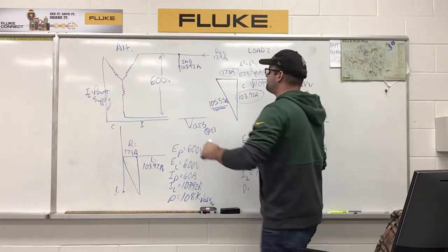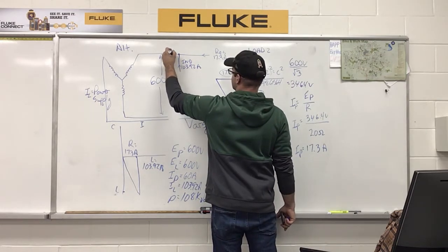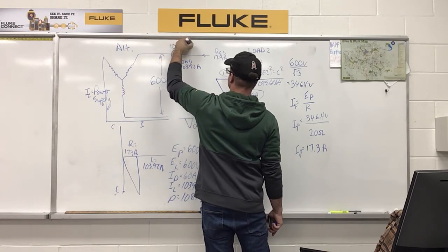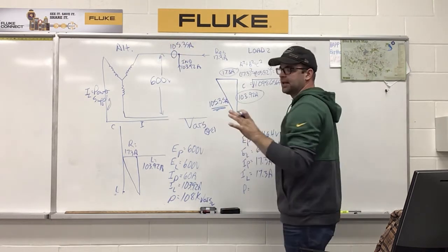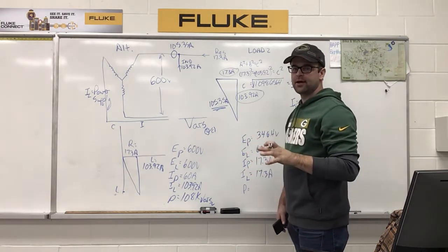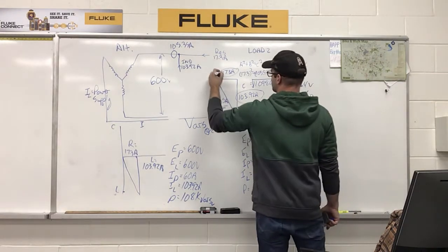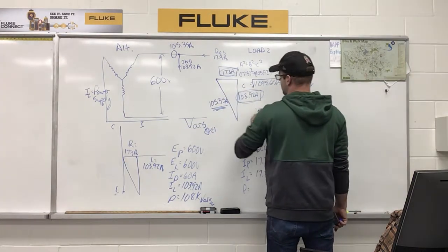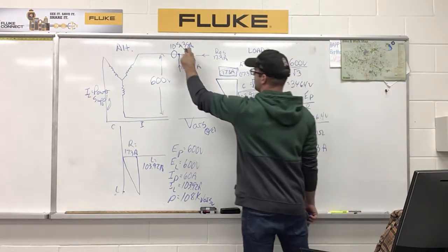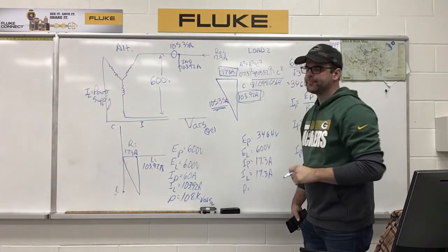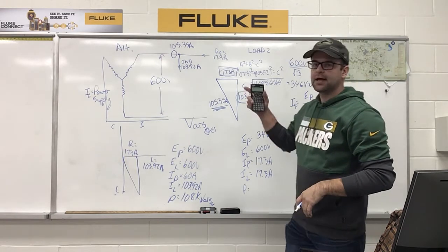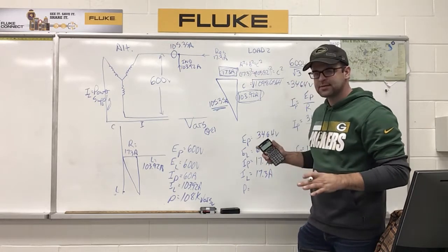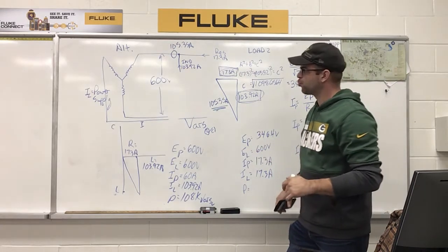So that value would be the value that is seen here. If I put an amp clamp here, it would say 105.35 amps. Remember, we used line values, and you can only use line values to calculate this out. So I have a line value here from my resistive load, I have a line value here from my inductive load. So if I'm using a line value and line value, this value here has to be a line value. When you're looking at Y-connected power supplies, if you forgot this point, you still would get the answer right.